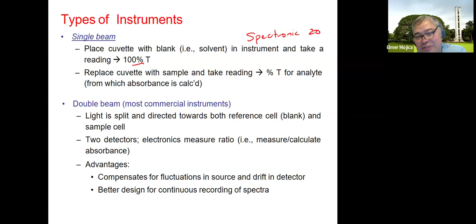So here in the double beam, the light is split and directed towards both reference cell and the sample cell. You have two detectors, okay, that measure the ratio. So it measures and calculates the absorbance. The advantage of this is it compensates for the fluctuations in the source and in the detector because you're getting the signal from the sample and the blank at the same time. Kaysa yung sa blank muna and then sample. So what if there's a fluctuation in the source? So there's a different reading there. So in addition to the sample, there could be a difference doon sa fluctuation na nangyari.